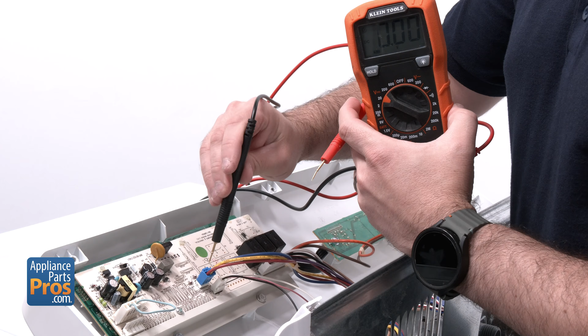Set your meter to volts DC, indicated by a V with a dotted or dashed line. Place the black meter probe on the red wire at connector J7 and leave it there. Touch the red probe to the blue wire. You should see 12.8 volts DC.